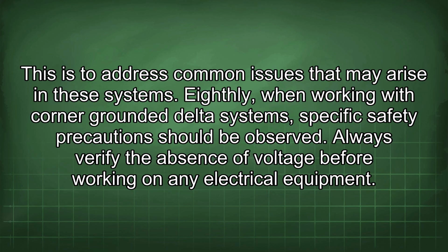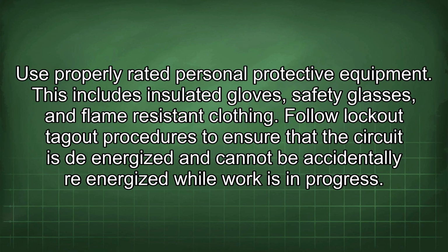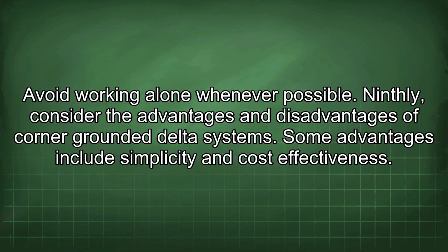Eighthly, when working with corner-grounded delta systems, specific safety precautions should be observed. Always verify the absence of voltage before working on any electrical equipment. Use properly rated personal protective equipment. This includes insulated gloves, safety glasses, and flame-resistant clothing. Follow lockout-tagout procedures to ensure that the circuit is de-energized and cannot be accidentally re-energized while work is in progress. Avoid working alone whenever possible.